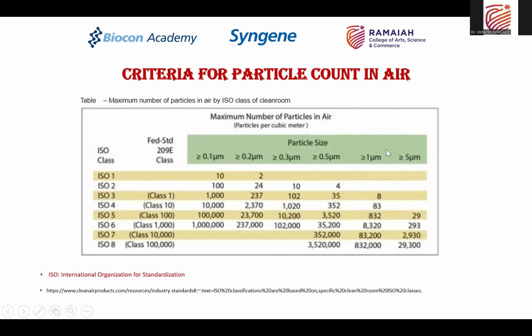This table gives you an idea of how many maximum non-viable particles are allowed in the air of particular industrial processes, clean rooms, etc. According to these standards, the particle count has to be monitored and kept under control for any industrial process. Wherever industrial processes are happening, in the clean rooms, the standards have to be monitored.